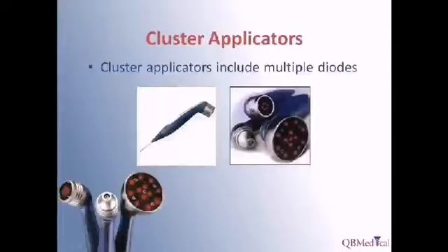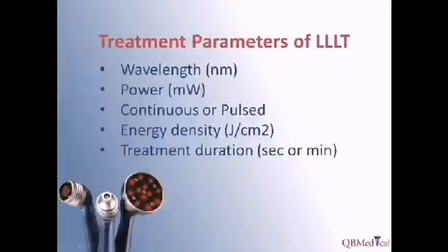Cluster applicators may contain diodes of varying light sources in order to expand the size of the treatment area and elicit therapeutic effects at different penetration depths. Now that we understand what a cold laser is, let's take a look into some of the specific treatment parameters.